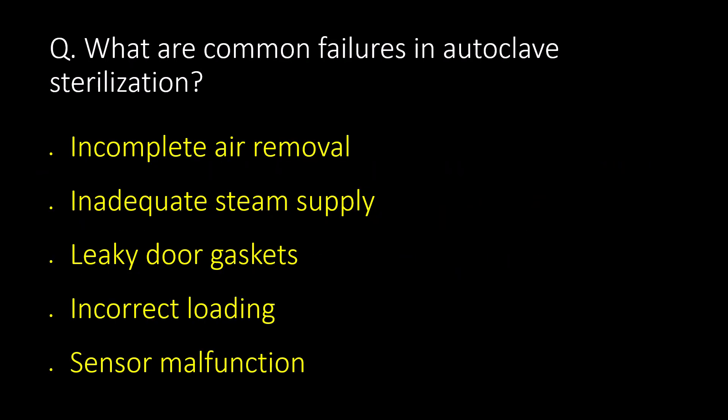A very commonly asked question: what are common failures in autoclave sterilization? Incomplete air removal, inadequate steam supply, leaking door gaskets, incorrect loading, and sensor malfunction are the common failures in an autoclave sterilization cycle.